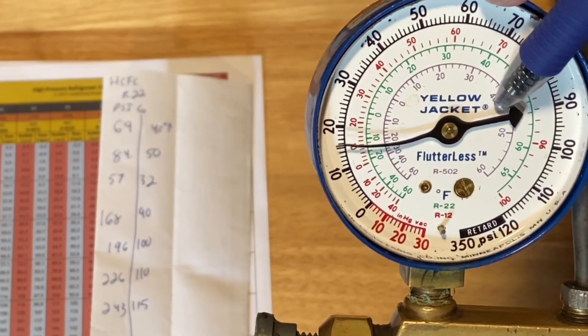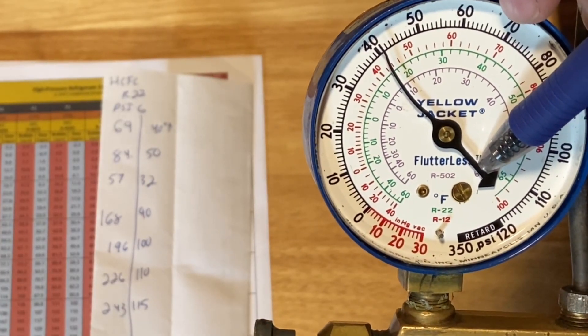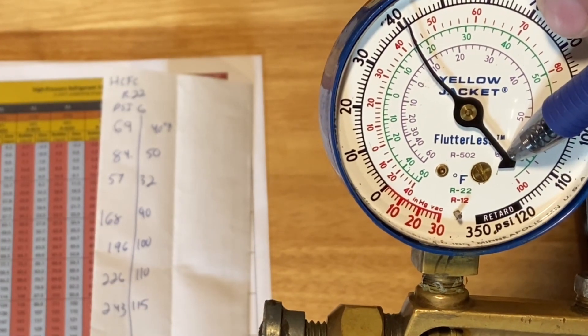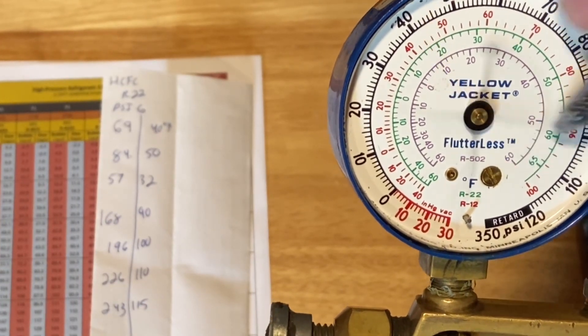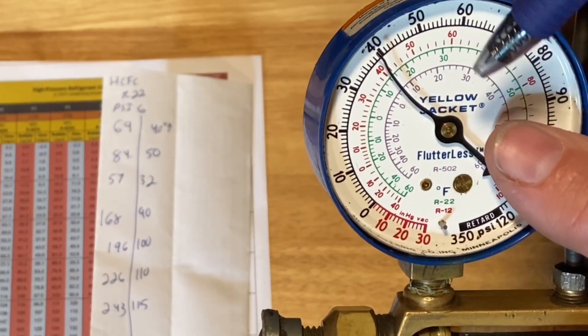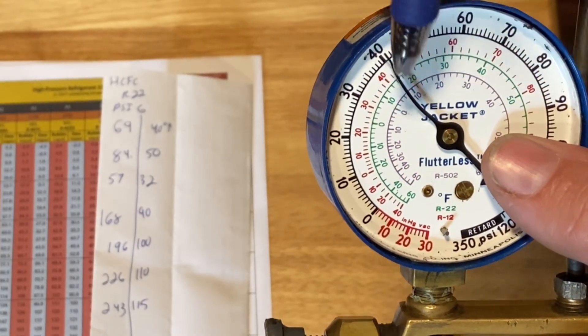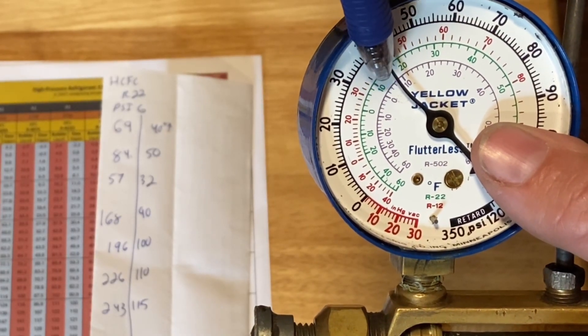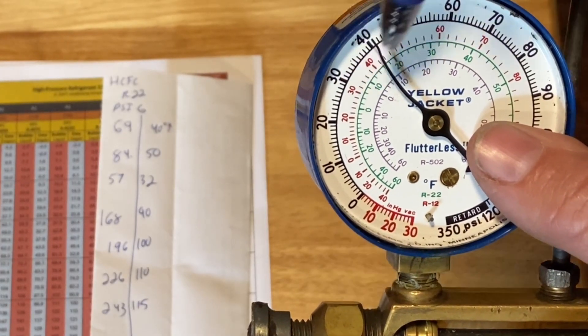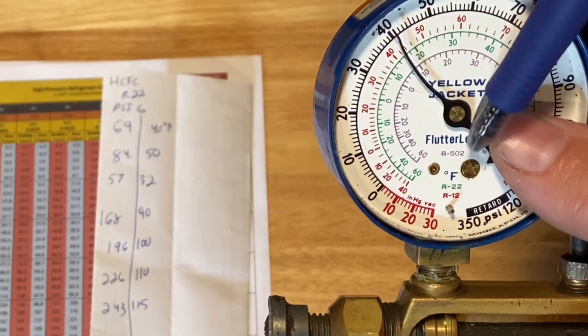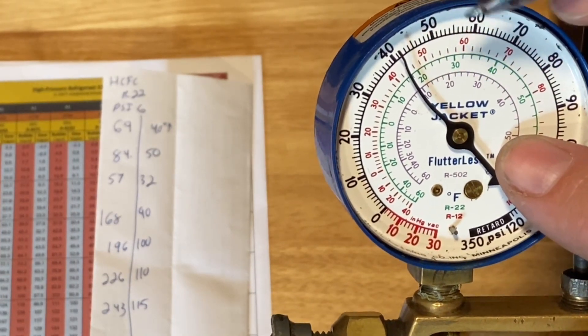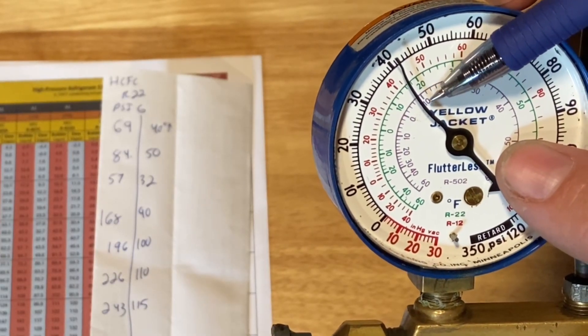Let's take a look at some examples. Let's say that my needle was pointing at, we'll do 40 psi gauge. We look at the next line on here and it's red and it's pointing at about 42 degrees Fahrenheit and that red line is R12. The next line down is R22. That's green. So if you follow the green line as it's pointing at 40 degrees here. We're at about 16 degrees Fahrenheit and if we're using in this case this pink line which is 502 at 40 psi gauge, it would also be a saturated temperature of about 8 degrees Fahrenheit.